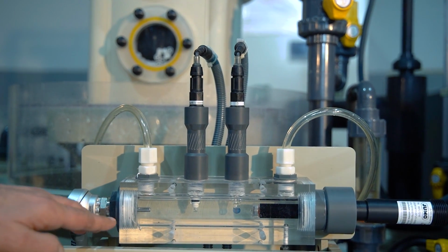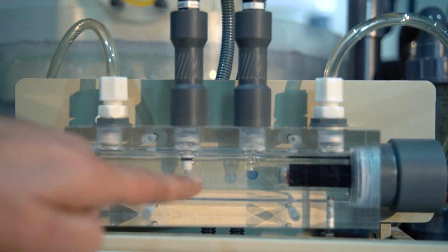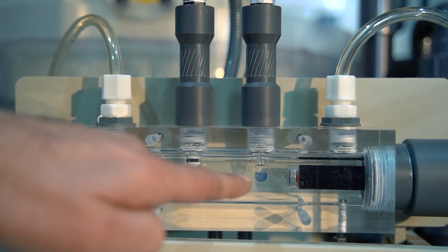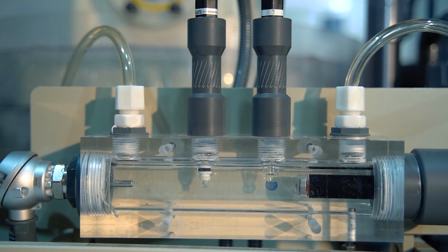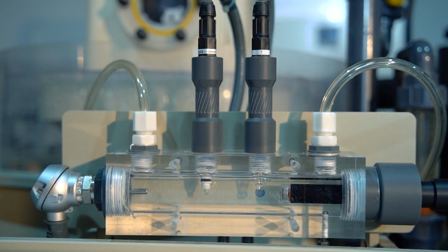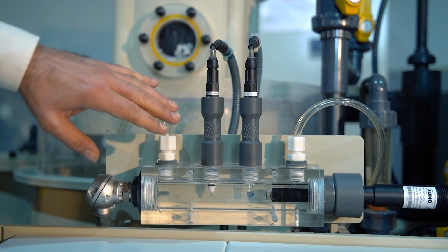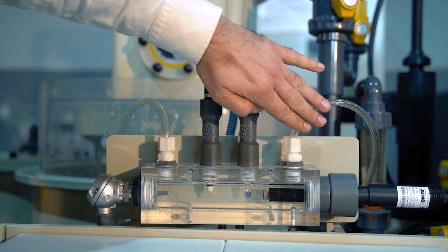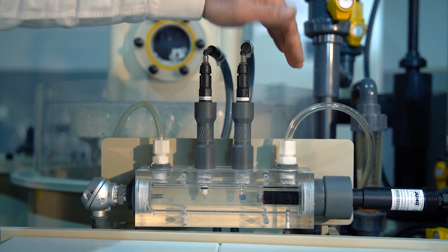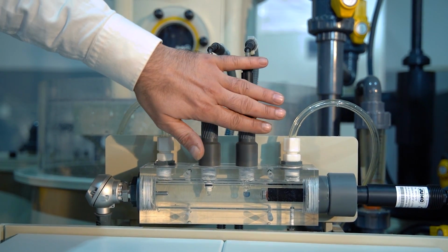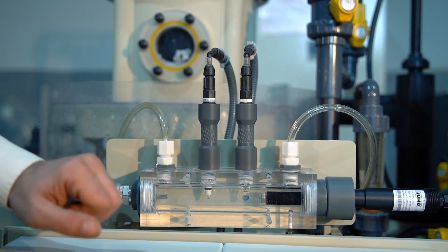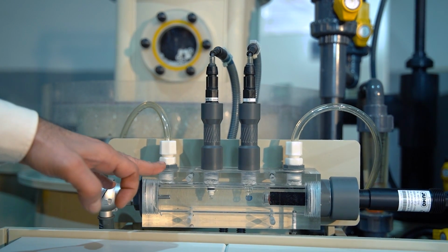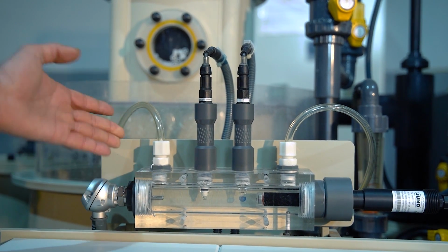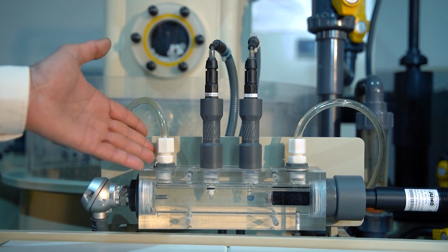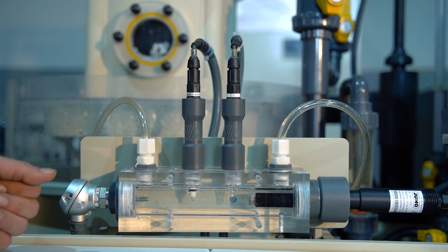So without opening or interrupting the flow, we can see if the measurement part of the probes is clean and effective. And also, for a replacement or any kind of service, we can easily bypass our water inlet, and while the unit is still processing, we can change the probes, we can clean the probes. As I said, this unit is holding 4 different probes, but our probe stations can be extended up to 10 different types of probes with different adapters.